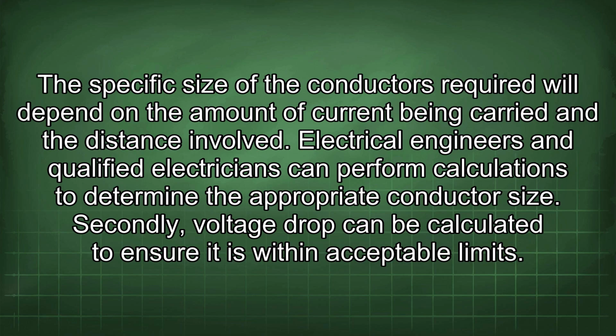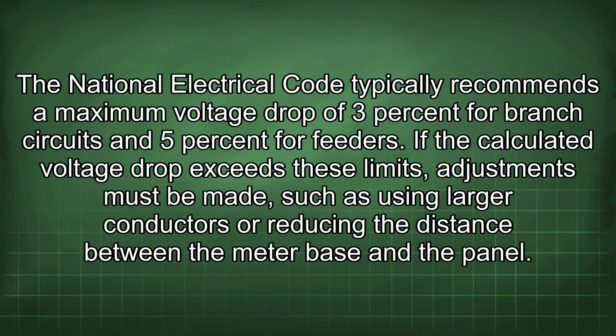Secondly, voltage drop can be calculated to ensure it is within acceptable limits. The National Electrical Code typically recommends a maximum voltage drop of 3% for branch circuits and 5% for feeders. If the calculated voltage drop exceeds these limits, adjustments must be made, such as using larger conductors or reducing the distance between the meter base and the panel.